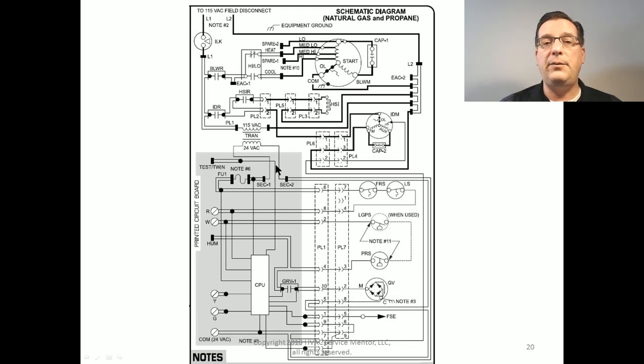What's next? Igniter has to glow. Where does the igniter get its voltage from? It comes through another relay that is in series with the draft inducer relay. So once the draft inducer relay closes, now we have a voltage supply for the hot surface igniter relay. When that relay closes, 120 volts comes out of the board and comes to the hot surface igniter.